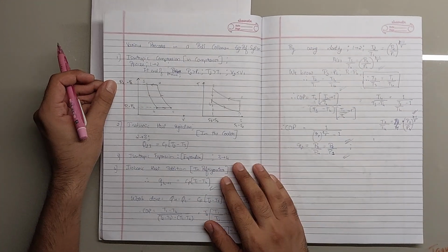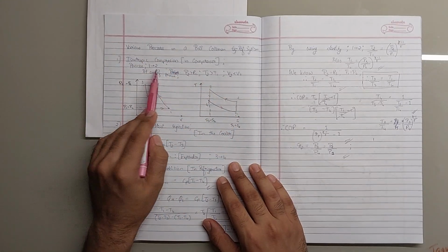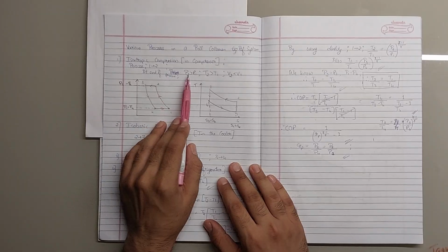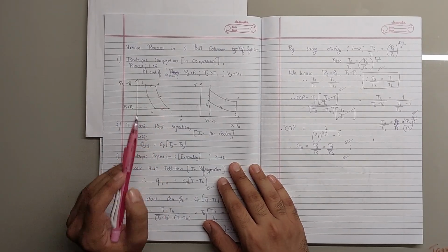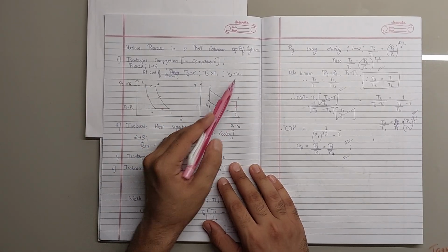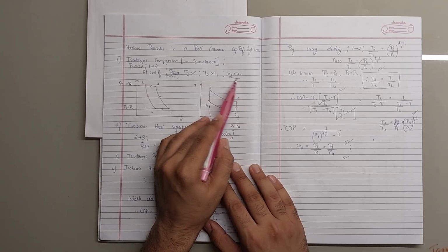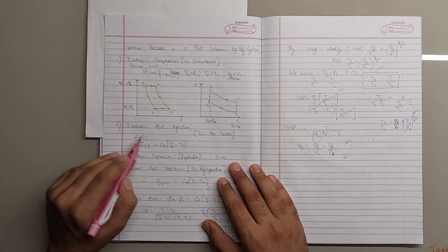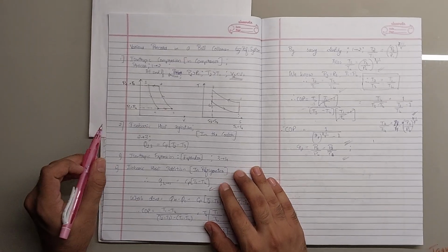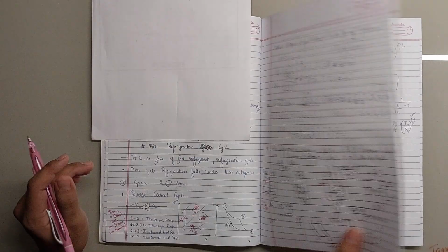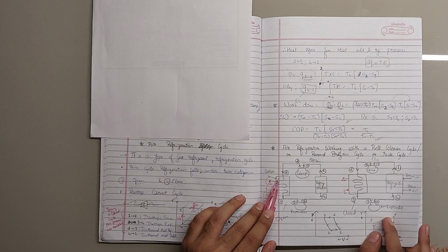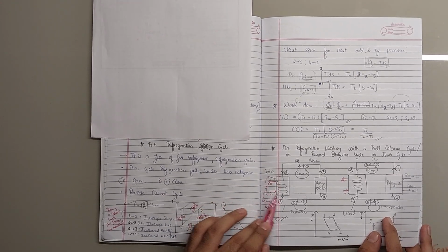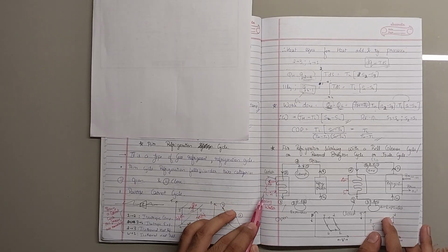So we can see the various processes. Isentropic compression from point 1 to 2, process 1 to 2. At the end of the process, P2 is greater than P1, the pressure increases, obviously the temperature increases, but as it is a compression, the volume decreases after the compression. Then we see isobaric heat rejection at the cooler. At the same pressure, the heat is rejected from the hot air to the cooling water.